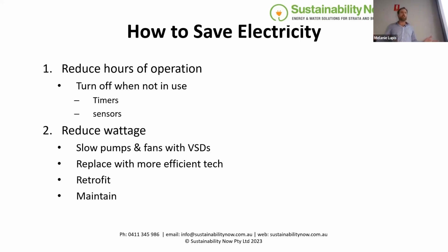All right, so how do we save electricity? Number one, reduce the hours of operation. That's the easiest thing. Just don't run it as much if we can. We can use timers and sensors. The car park ventilation is a good example, using sensors to not run those fans if they don't need to be. The other way: electricity consumption is electrical demand multiplied by time, so kilowatts times hours, kilowatt hours. Reduce one of those and you'll reduce your consumption. Reduce the hours or reduce the actual wattage.